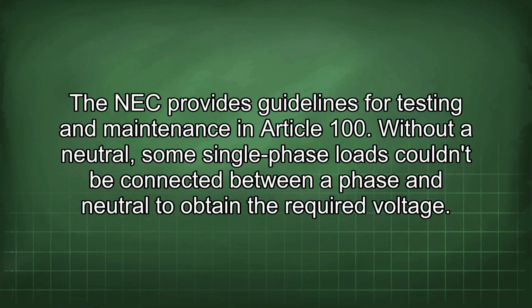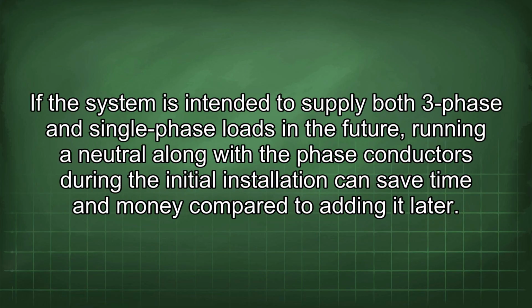Without a neutral, some single-phase loads couldn't be connected between a phase and neutral to obtain the required voltage. If the system is intended to supply both three-phase and single-phase loads in the future, running a neutral along with the phase conductors during the initial installation can save time and money compared to adding it later.